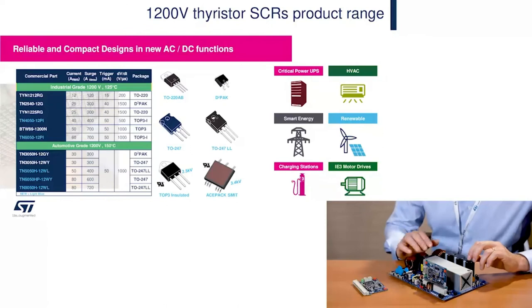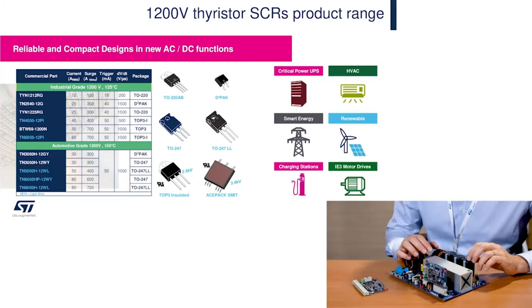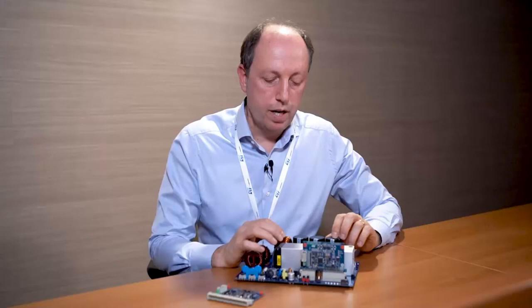On the same power board, a Thyristor SCR provides AC-line polarity switching with active current limitation at power-up or line drop recovery. When compared with bulky NTC plus mechanical relay circuits, the Thyristor SCR offers advantages in terms of smooth progressive but fast power-up, robustness to surge, no contact bouncing, and no EMI issues.